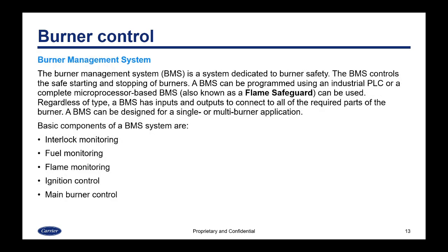The burner management system or BMS is a system dedicated to burner safety. The BMS controls the safe starting and stopping of burners. A BMS can be programmed using an industrial PLC or a complete microprocessor-based BMS, also known as a flame safeguard. Regardless of type, a BMS has inputs and outputs to connect all the required parts of the burner, and can be designed for single or multi-burner applications.